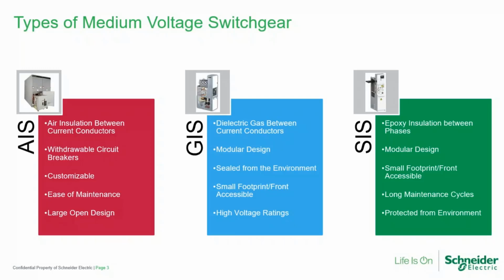If we move to the next category to the right, we're talking about the newest style of medium voltage switchgear, and this is a style we're referring to as solid insulated switchgear. Generally, an epoxy or a rubber-based solid insulator makes up the primary form of dielectric insulation in this style of gear, as opposed to gas in GIS or air separation in AIS. It has a lot of the same characteristics as gas insulated switchgear, in the sense that some of the biggest benefits are the modular design and very small footprint, and it brings with it a very long maintenance cycle. So reduced maintenance cost is also a great benefit of solid insulated styles of switchgear. And you can see an evolution of design styles here, going from AIS to GIS to SIS.